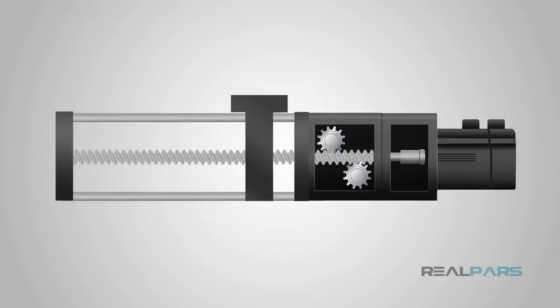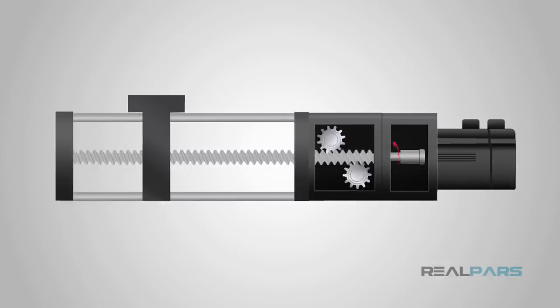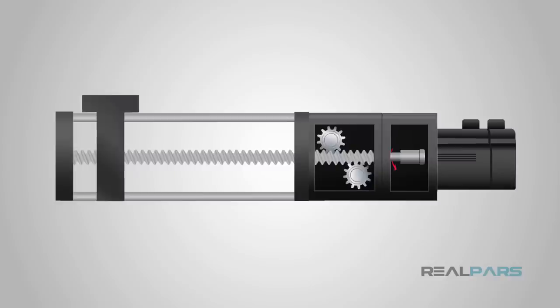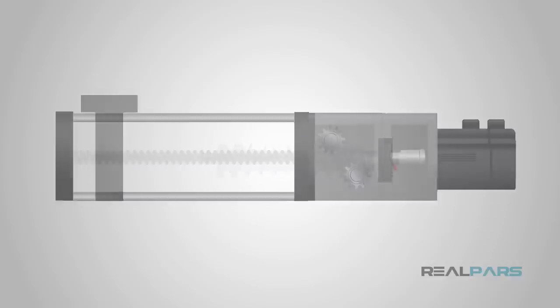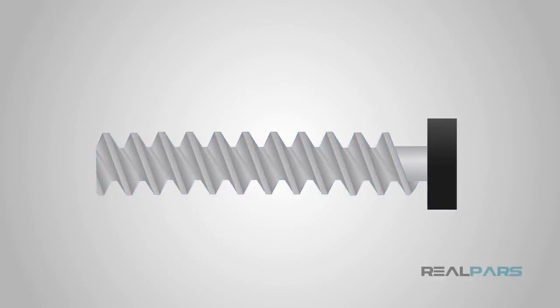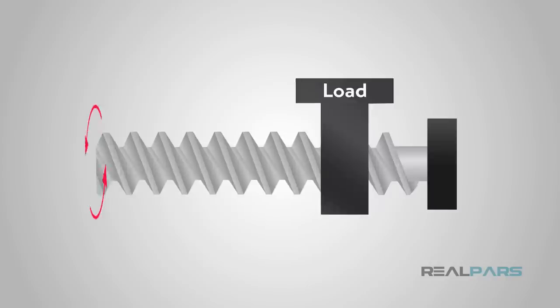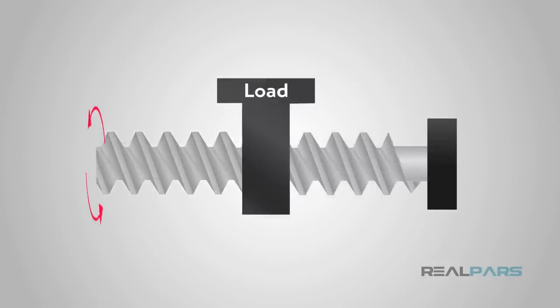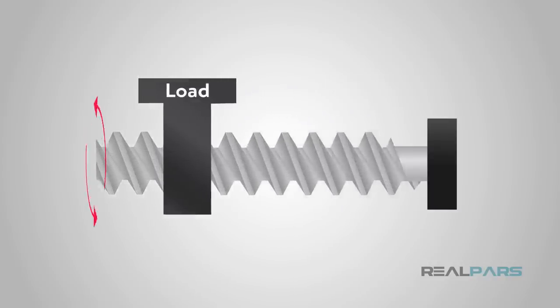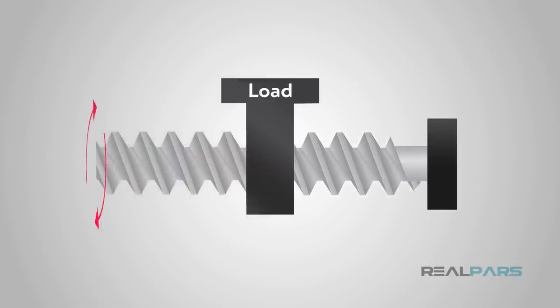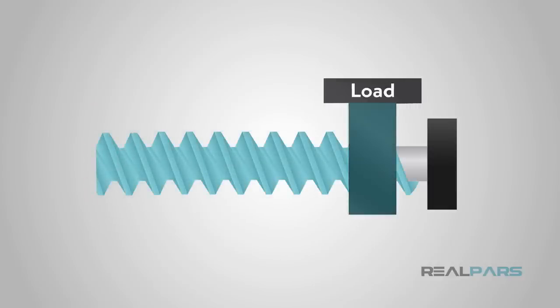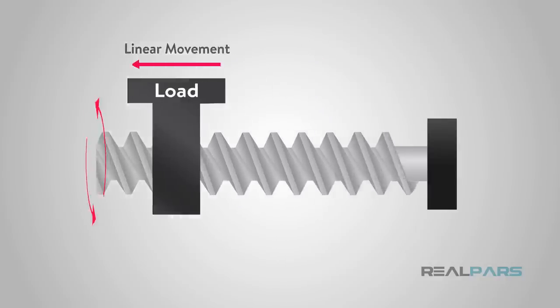Gears are used to allow a motor to be geared down to provide torque necessary to rotate the screw under a heavier load the motor would be capable of controlling directly. Rotary motion of the motor is converted into linear displacement of the actuator. A lead screw has a continuous helical thread machined on its circumference running along the length, similar to the thread on a bolt. Threaded onto the lead screw is a lead nut or ball nut with exact helical threads. The nut is normally fixed and prevented from rotating with the lead screw. When the lead screw is rotated, the nut is driven along the threads. The direction of motion of the nut will depend on the direction of rotation of the lead screw. Connecting the load to the nut, the motion can be converted to usable linear movement.